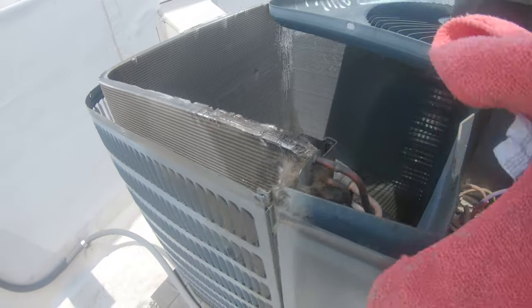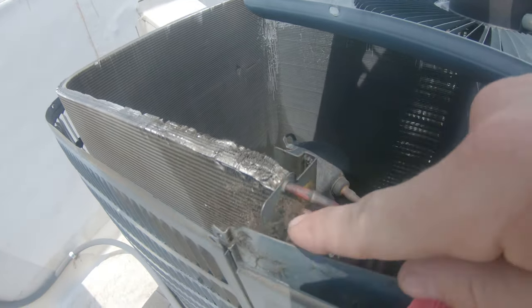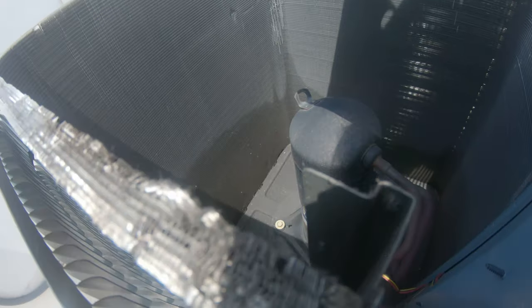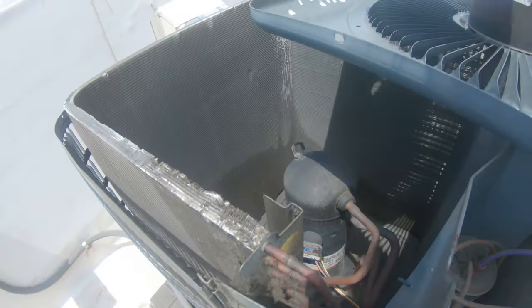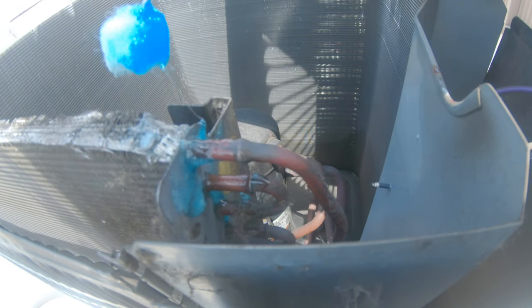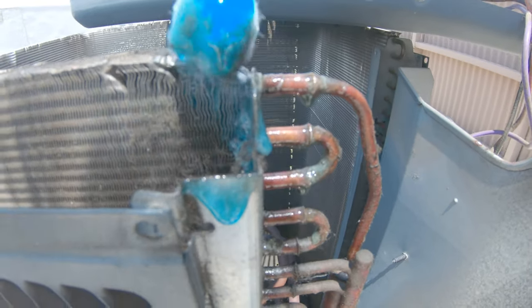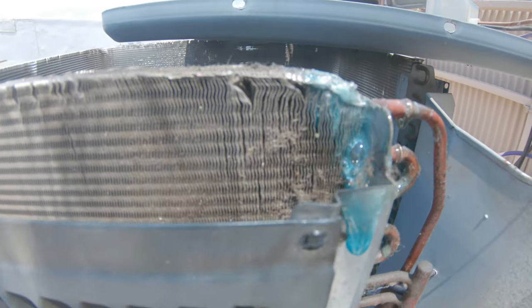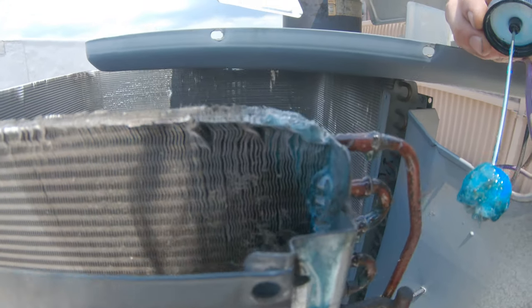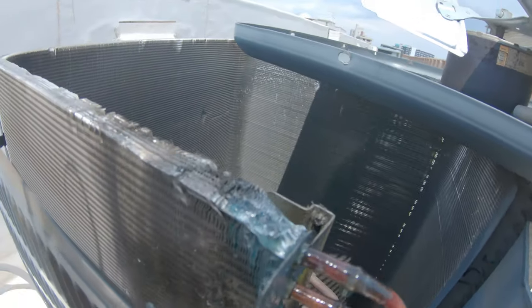This is about where I suspect the leak to be. It's usually right here, but we are going to verify that because we need to repair this. It's kind of hard to pinpoint with soap bubbles, but I know it's there — I can see the bubbles coming out. I don't know if it's going to be this top one or the one right below it. Let's find out though.